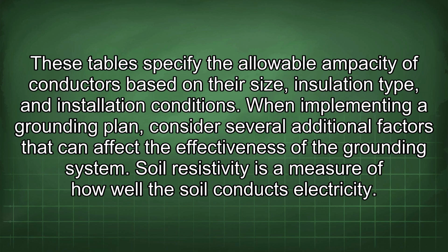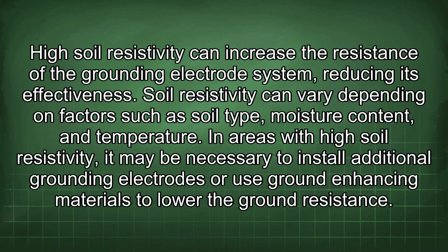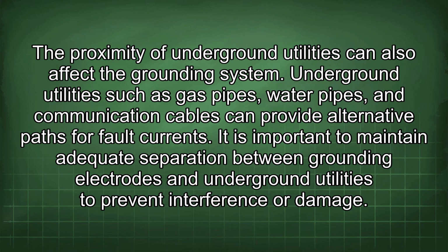When implementing a grounding plan, consider several additional factors that can affect the effectiveness of the grounding system. Soil resistivity is a measure of how well the soil conducts electricity. High soil resistivity can increase the resistance of the grounding electrode system, reducing its effectiveness. Soil resistivity can vary depending on factors such as soil type, moisture content, and temperature. In areas with high soil resistivity, it may be necessary to install additional grounding electrodes or use ground-enhancing materials to lower the ground resistance.